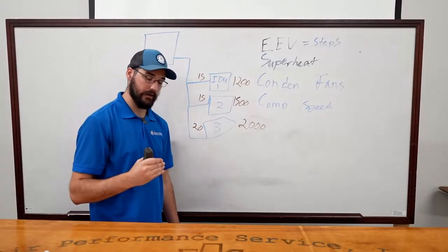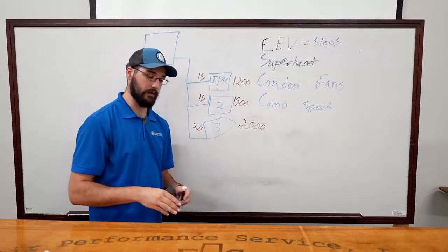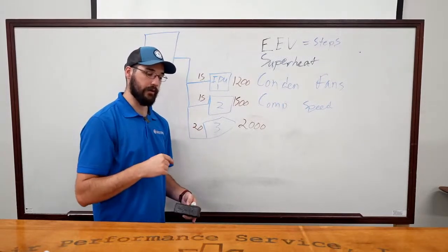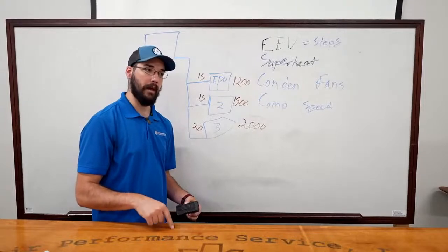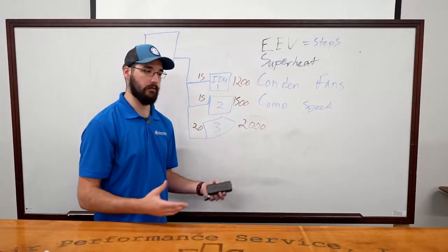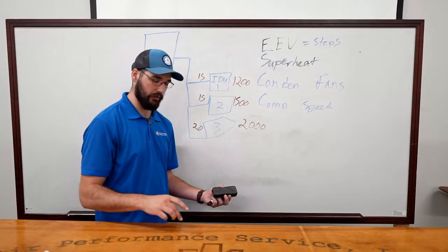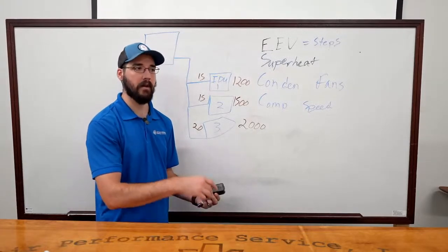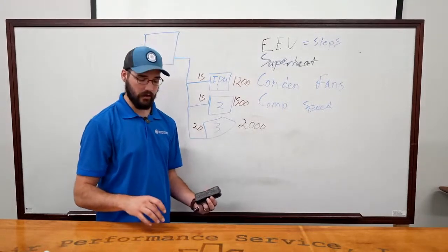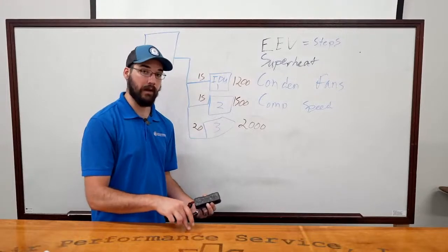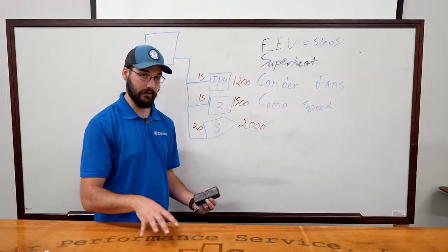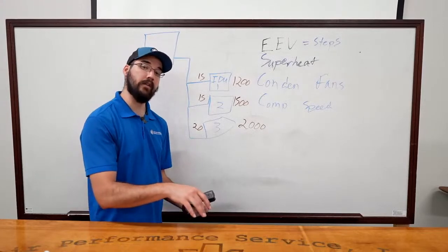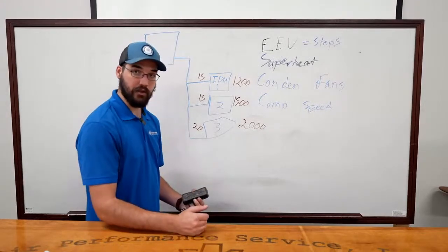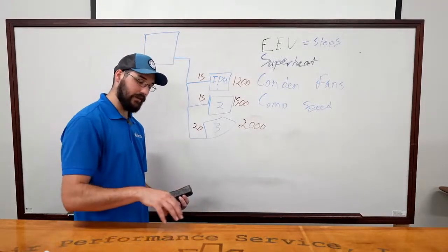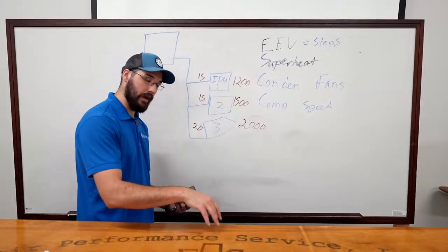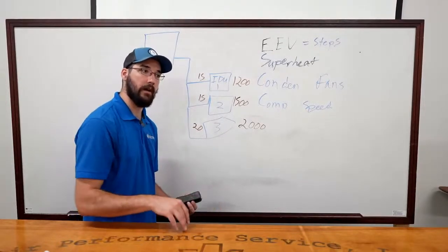The safer way would be to shut the system down and use your recovery machine to pump in a pound or two, depending on the size of the system. If it's a really big one, you may be able to go 3 to 4 or 5 pounds at a time. Most of the systems we work on, you should probably only go 1 to 2 pounds at a time, and that's it. And you would put that in on the liquid line coming out of the machine. So that's the safe way to do it, but you're waiting on the startup and shutdown time every time.